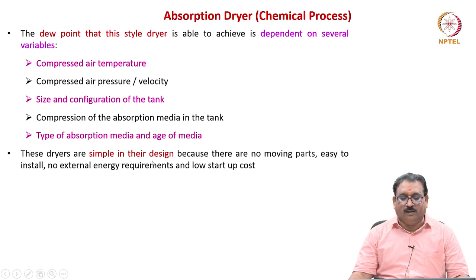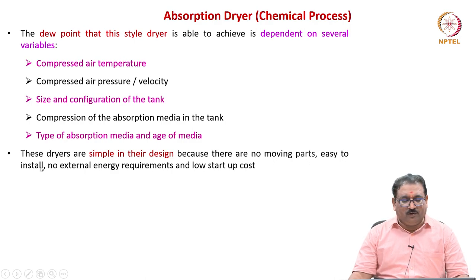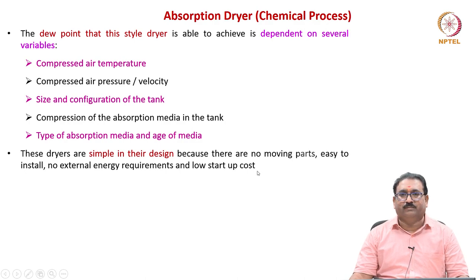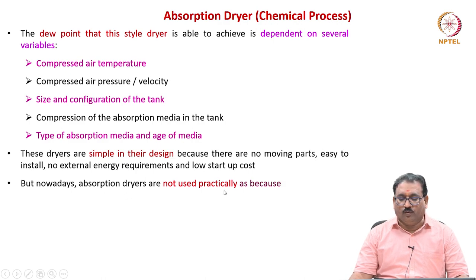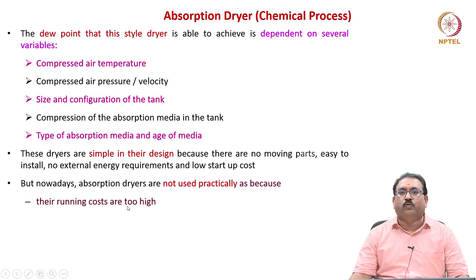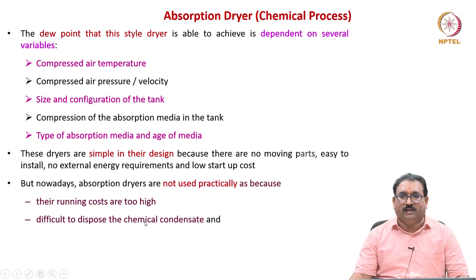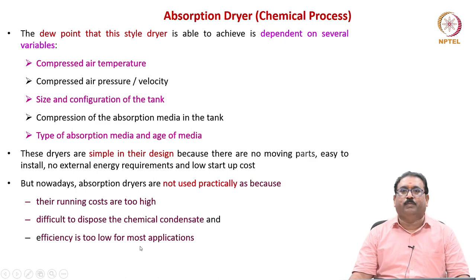These dryers are simple in their design because there are no moving parts, they are easy to install, require no external energy, and have low startup cost. However, absorption dryers are not used practically today because running costs are too high, chemical condensate disposal is difficult, and efficiency is too low for most applications.